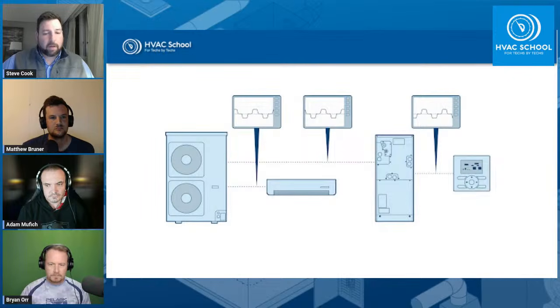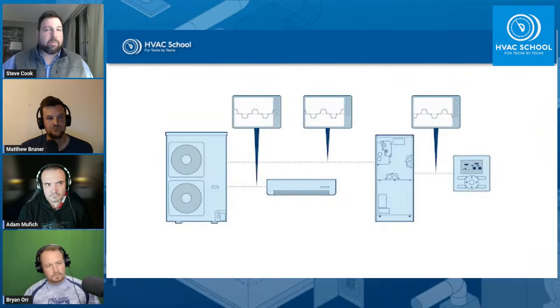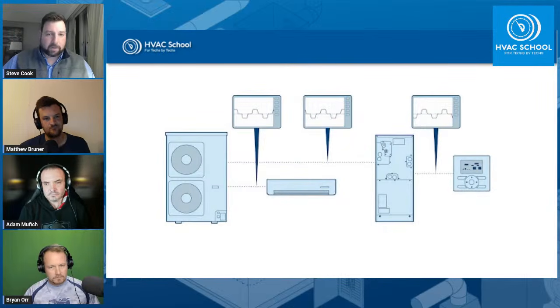But that signal, if I were to put that same wire on just the indoor unit and remove it from the outdoor unit, unless it's a complete circuit, like a daisy chain, you likely will not see the carrying signal. That carrying signal comes from the outdoor unit power source. And when I say carrying signal, I mean the communication voltage bus. So, like I was saying earlier, Hisense is 5 volts DC, Daikin 16, Mitsubishi's 29. That's the signal that really pushes it along. And then the pulses are a fraction of that. They're not actually 29 volts.